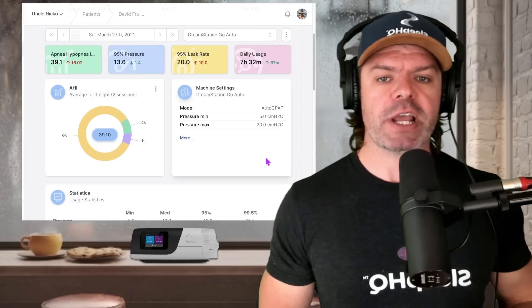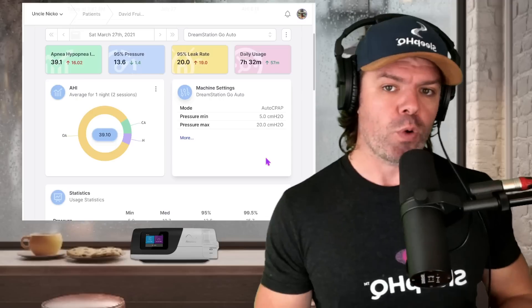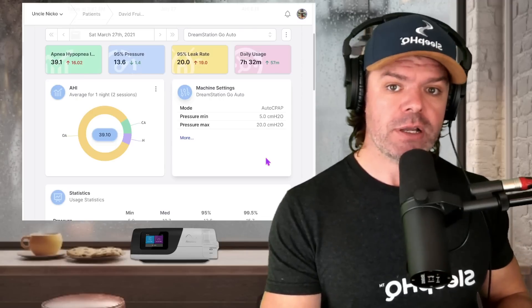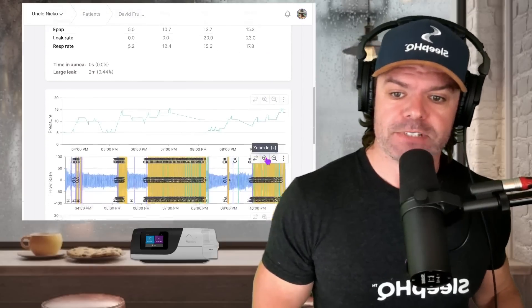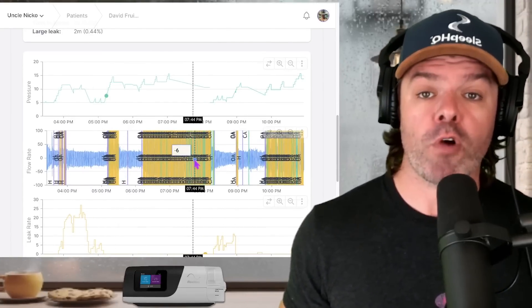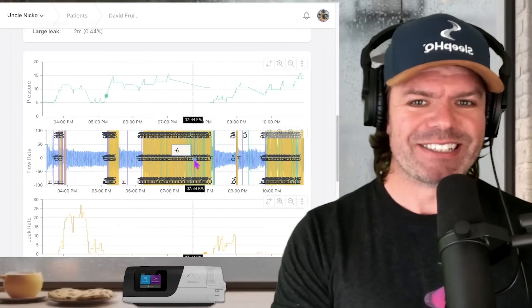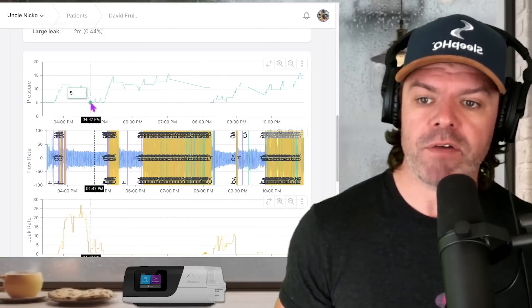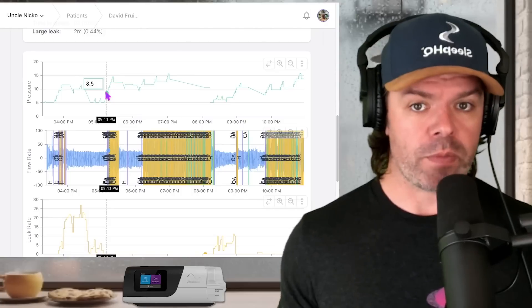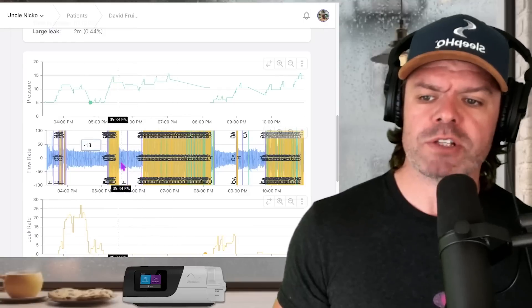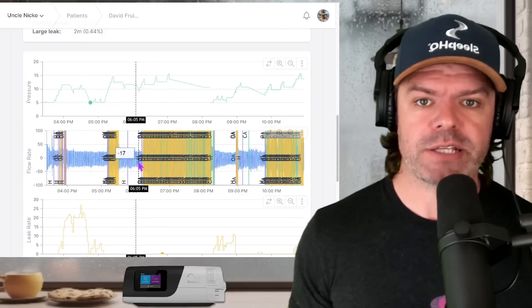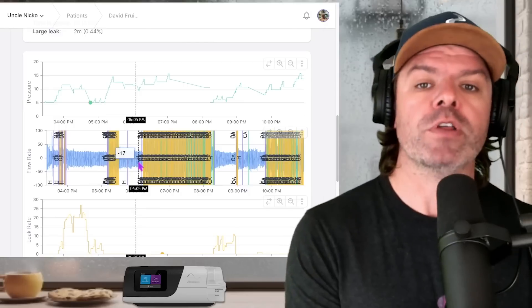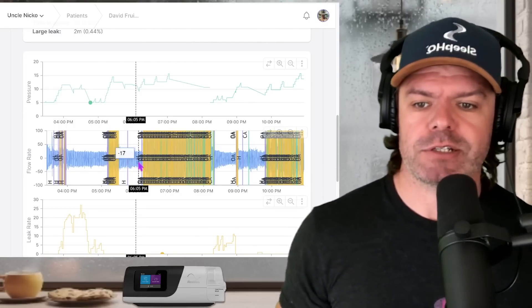Let's scroll down and check out Dave's breathing and let's see how the Philips auto algorithm is changing the pressure in response to Dave's obstructive events. Here we go. So this section right here, the flow rate is Dave's breathing. Every breath he takes, we can see in high definition on Sleep HQ, which is really cool. And just above it, we have the pressure changes. This is the automatic algorithm changing the pressure over time in response to what's happening on the flow rate. And every manufacturer has their own specific unique auto algorithm, their own formula that they use to determine the pressure changes.